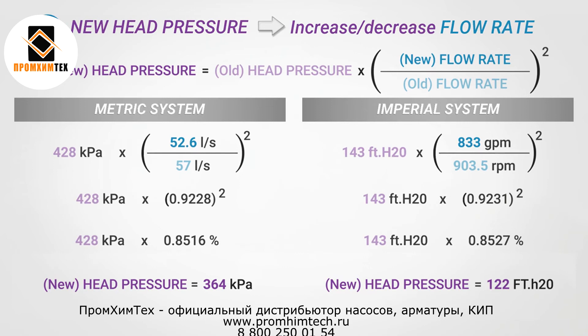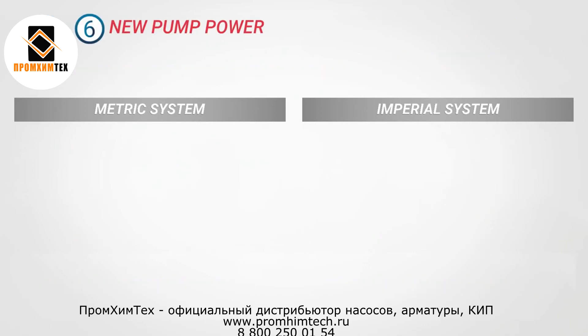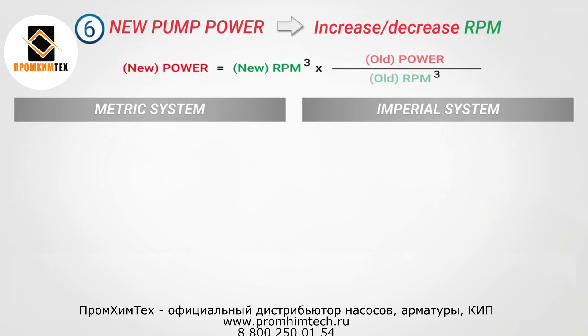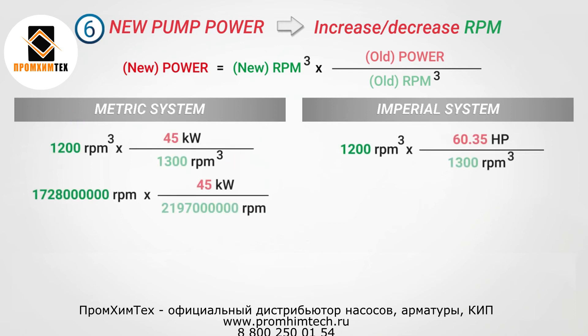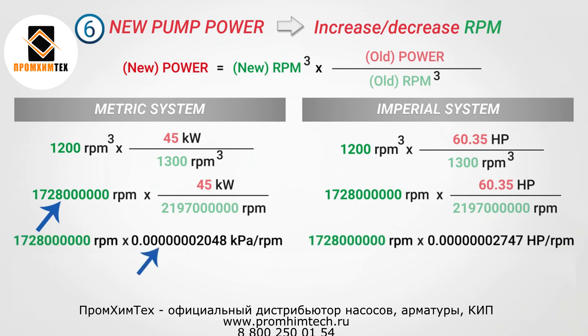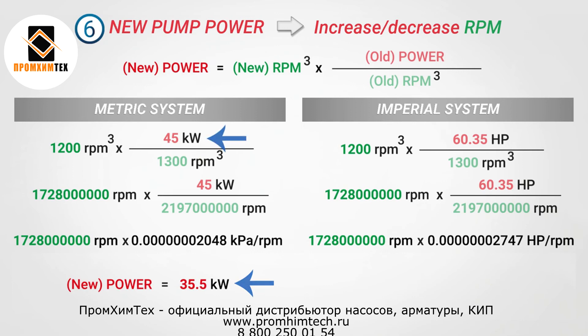The next step is to calculate the pump power, which is the power consumed by the pump in order to move and increase the pressure of a fluid. The power requirement depends on several factors, including pump motor efficiency. To calculate the new power when changing RPM, we cube the new RPM and multiply it by the division of the old power by the old RPM cubed — make sure to cube both RPM values. The result shows the new power comes down to 35.5 KW compared to the initial 45 KW. In the imperial system, the power comes down from 60.35 HP to 47.5 HP.